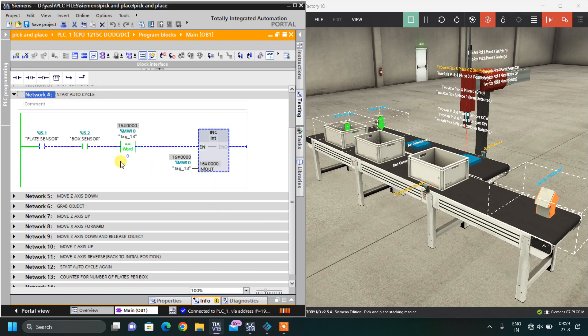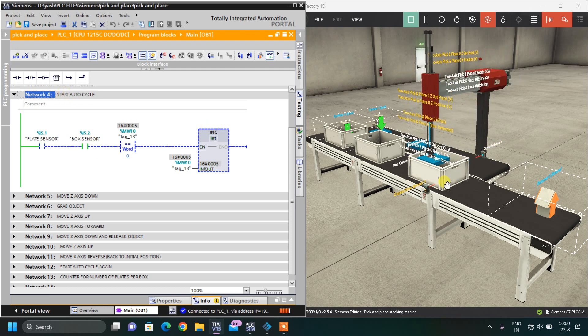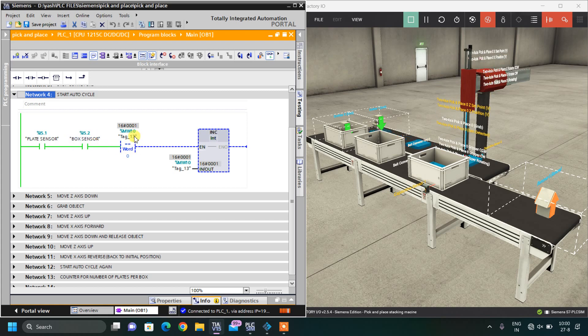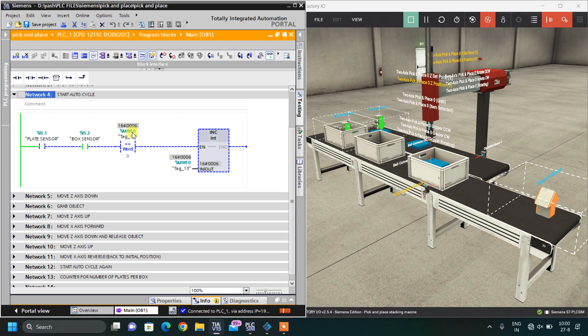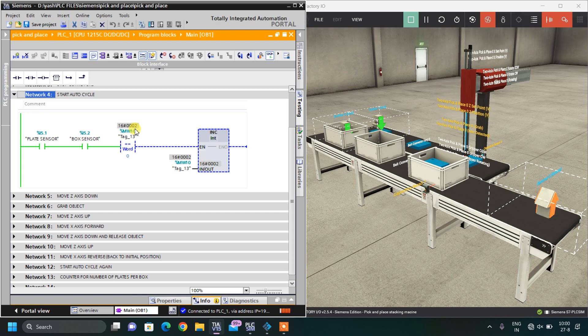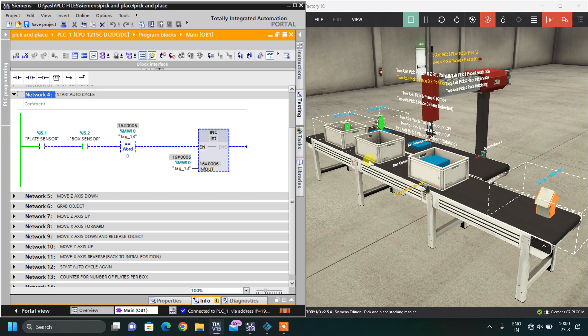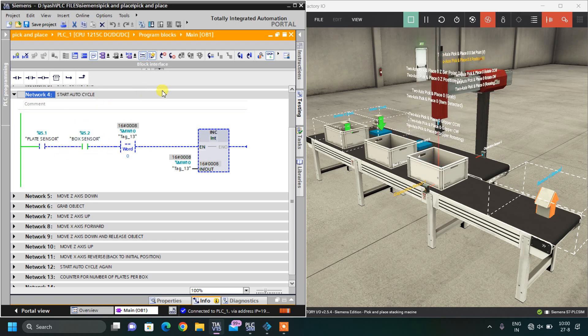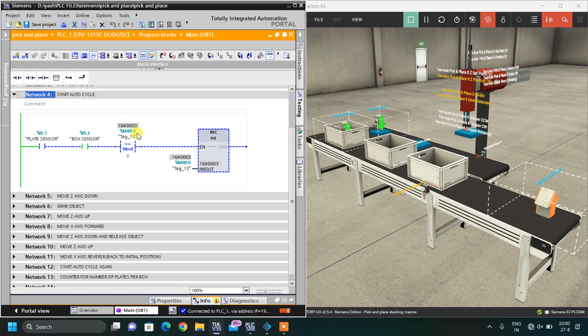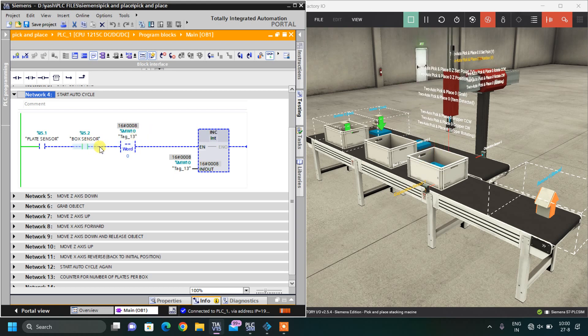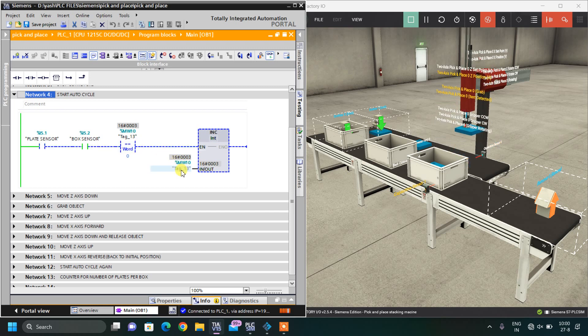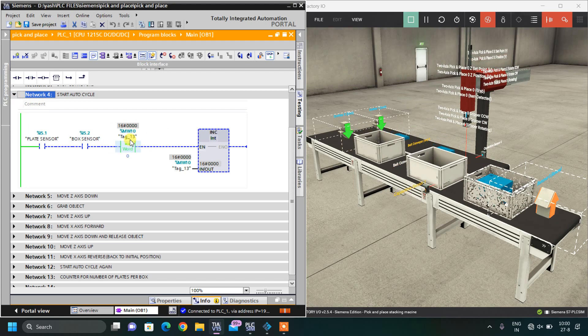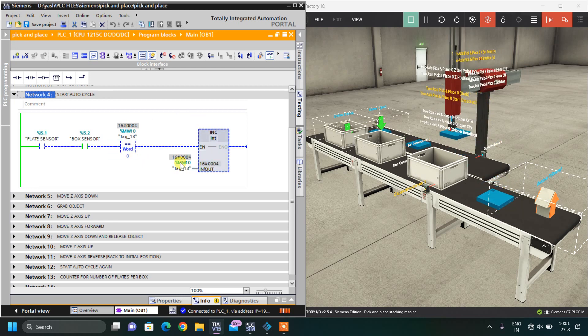Here is the important network — start auto cycle. When both sensors are on, the other condition is MW10, my memory word for auto process. It goes up to 8 values in one auto process because there are 8 steps in one cycle, after which it becomes 0. So when this auto bit is 0 and both sensors are on, I increment MW10 by 1 using a comparison block. Initially it is 0 and when both sensors are present, MW10 increments to 1.